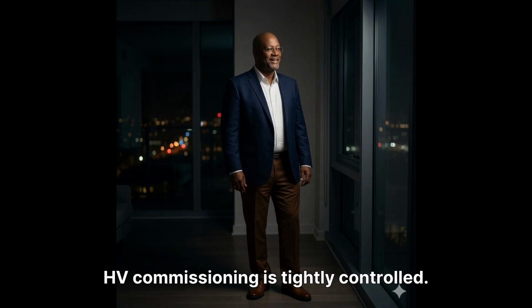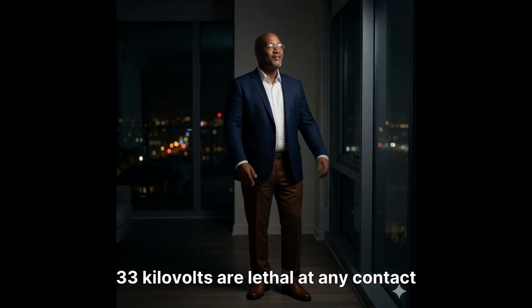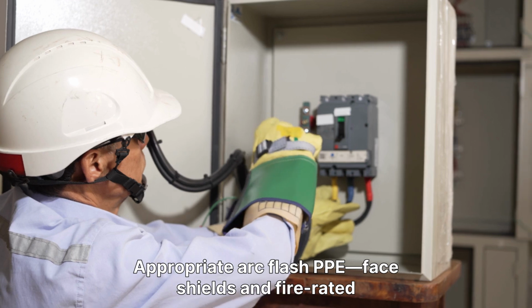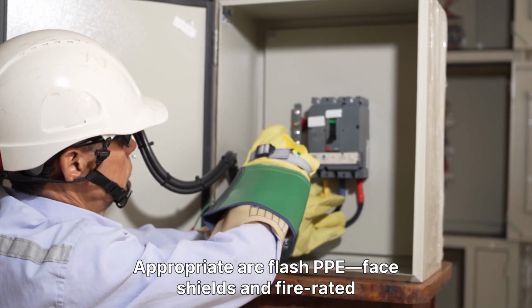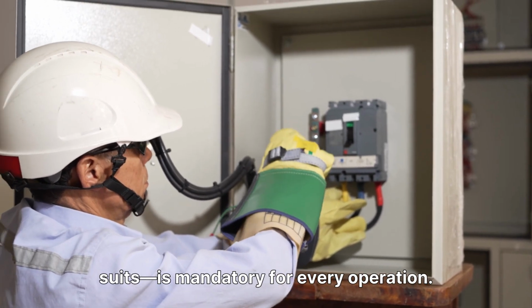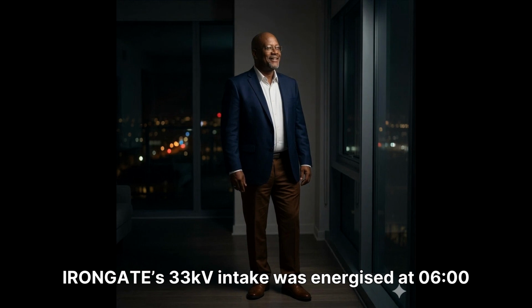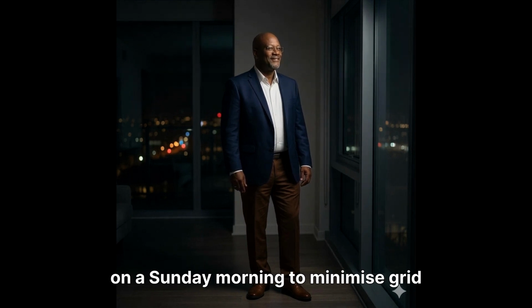HV commissioning is tightly controlled. 33 kilovolts is lethal at any contact distance. Appropriate arc flash PPE, face shields and fire-rated suits, is mandatory for every operation. IRONGATE's 33 kV intake was energized at 06:00 on a Sunday morning to minimize grid load.